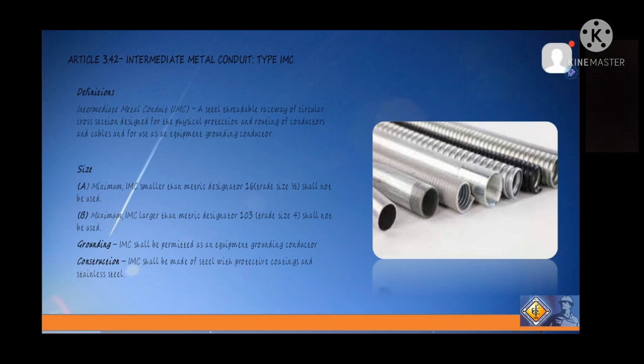Next is for the size. So for the size of our type IMC, for the minimum, IMC smaller than metric designator 16 with a trade size of 1/2 shall not be used. And for the maximum, IMC larger than metric designator 103 or trade size number 4 shall not be used. For the grounding, IMC shall be permitted as an equipment grounding conductor. And for the construction, IMC shall be made of steel with protective coatings and stainless steel.